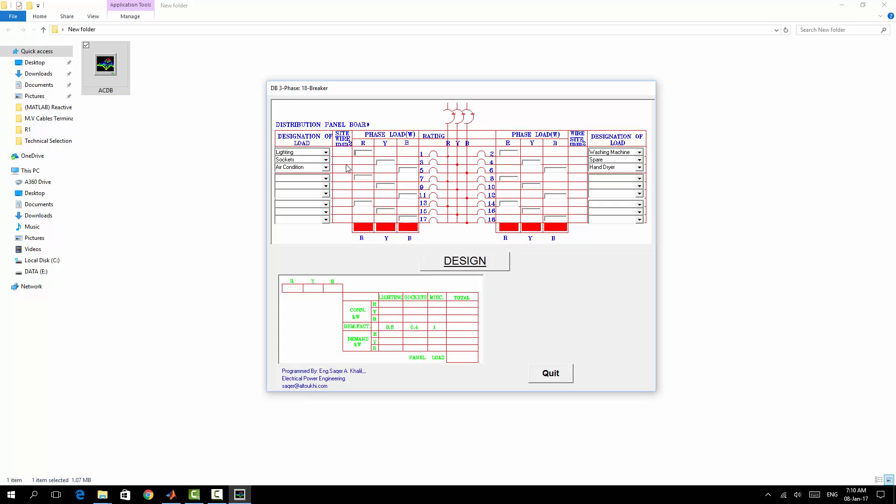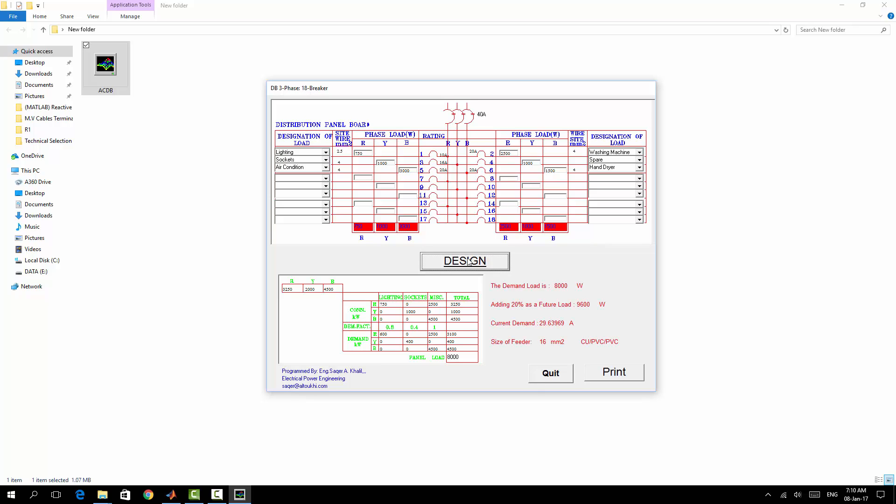For sockets 1000, for air conditioning 3000, for washing machine 2500, spare 1000, and dryer 1500. So simply by clicking design, first of all you are going to find the appropriate wire size: 2.5 square millimeter, 4, 4, 4.